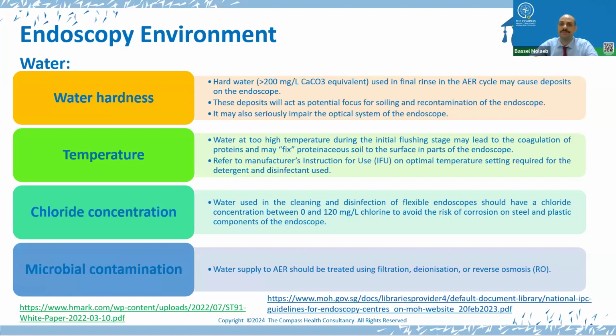Temperature of the water is important. Too high a temperature during the initial flushing stage may lead to coagulation of the proteins, and cause fixation of the protein soiling on the surface of the endoscope. So you need to refer to the manufacturer's instructions for use to select the optimal temperature that is required for the detergent and disinfectant that is used.